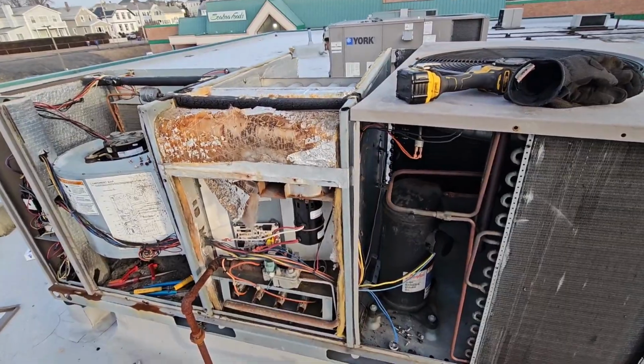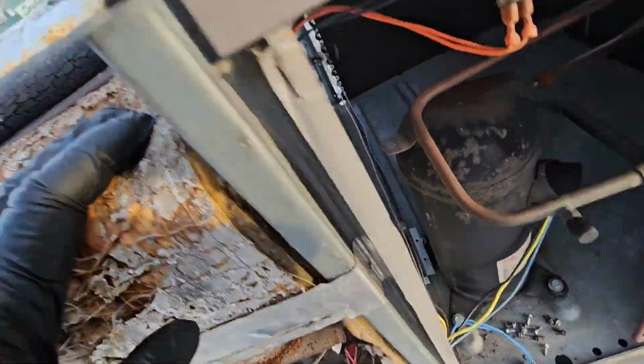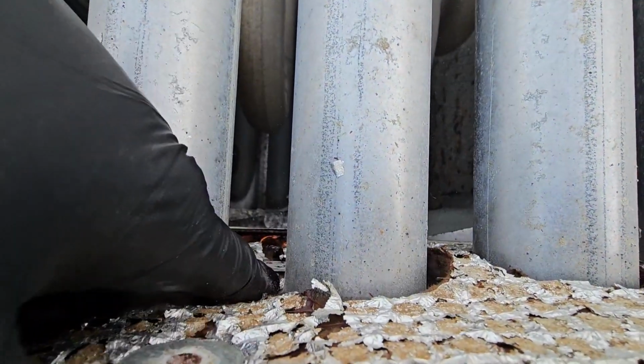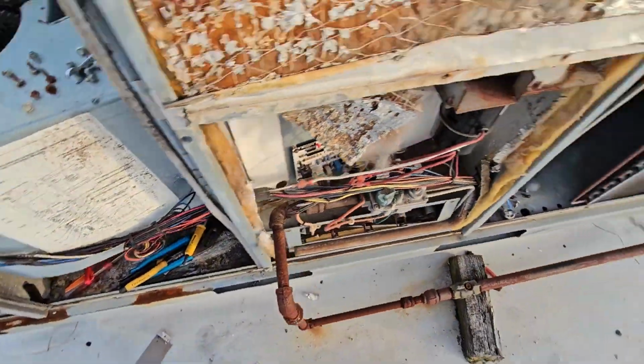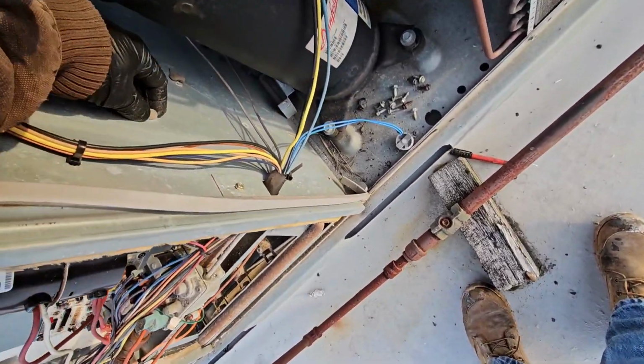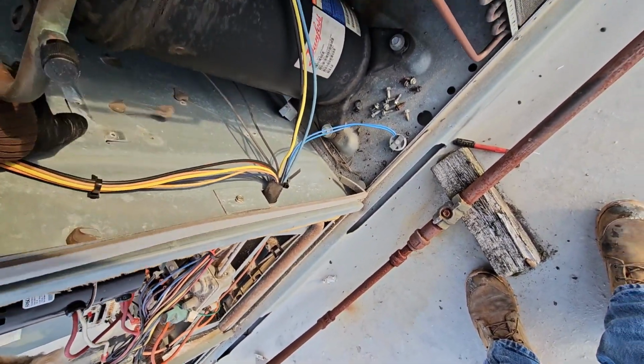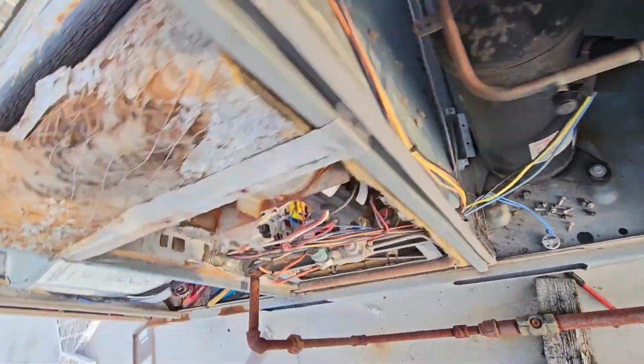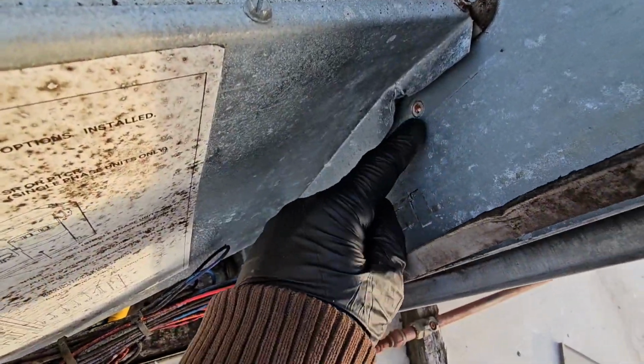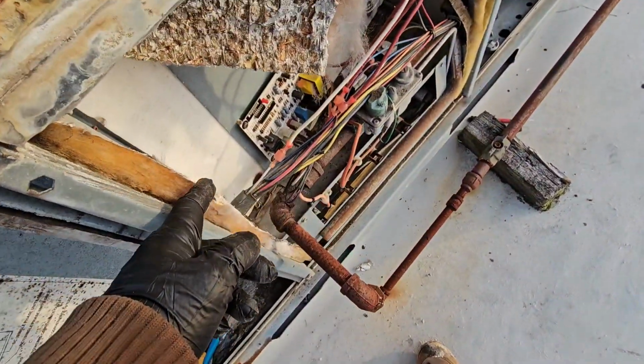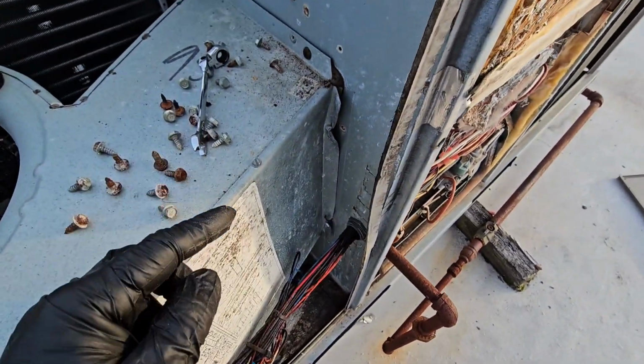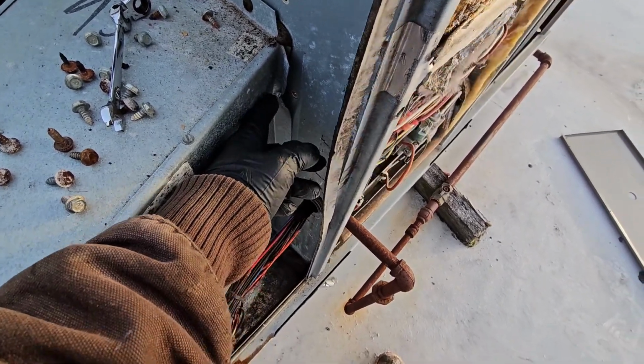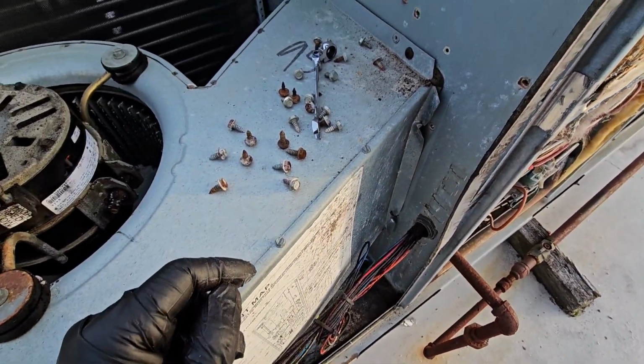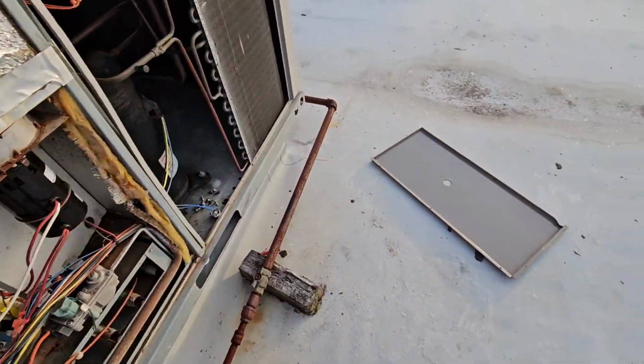Alright, so the biggest thing about the York units is there's screws in places you don't really see. There were screws down here. I don't know if some of these holes are covered with silicone, but there's no screws in them. You gotta get all these little screws on the side. I had to bend these back to get the screws, because that holds, I think it holds the heat exchanger in two pieces. So I have to get my flange pliers and my hammer after, and straighten this out. Yeah, not exactly a quick heat exchanger change out.